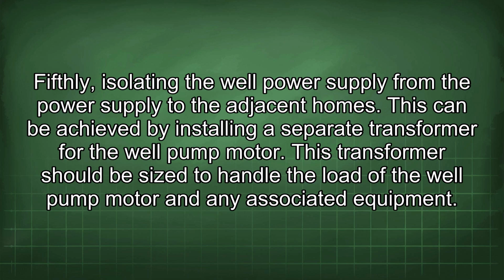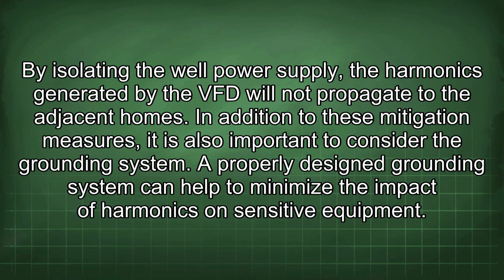Fifthly, isolating the well power supply from the power supply to the adjacent homes. This can be achieved by installing a separate transformer for the well pump motor. This transformer should be sized to handle the load of the well pump motor and any associated equipment. By isolating the well power supply, the harmonics generated by the VFD will not propagate to the adjacent homes.